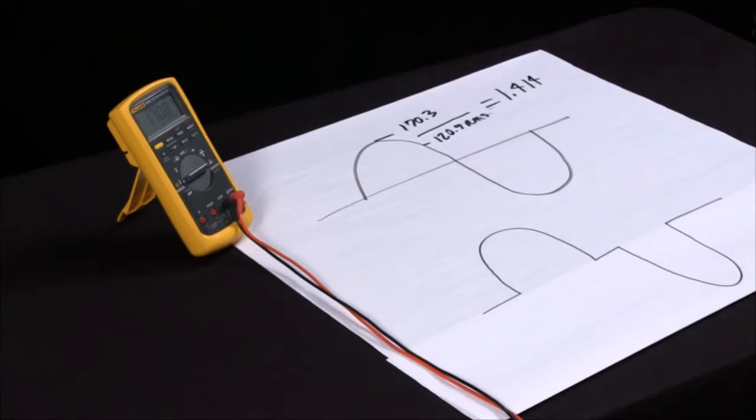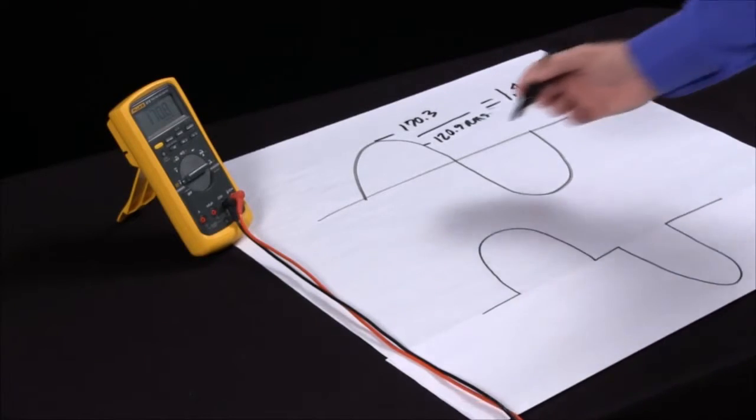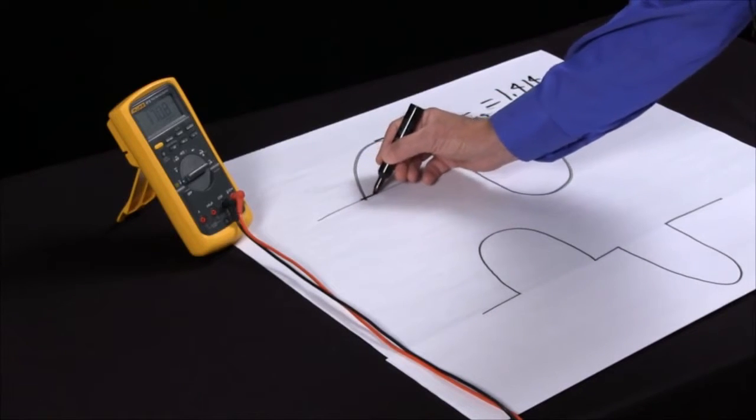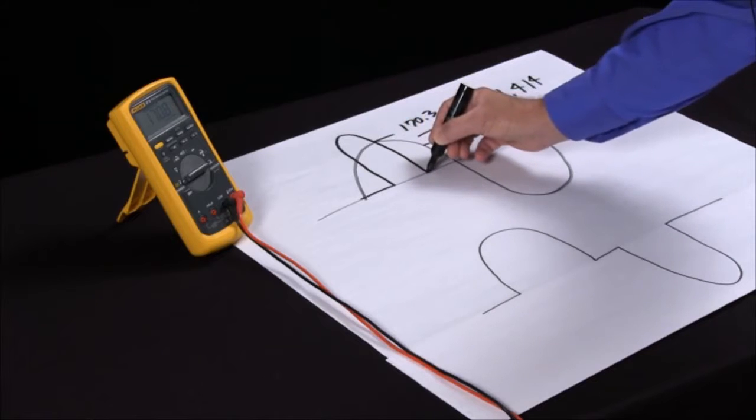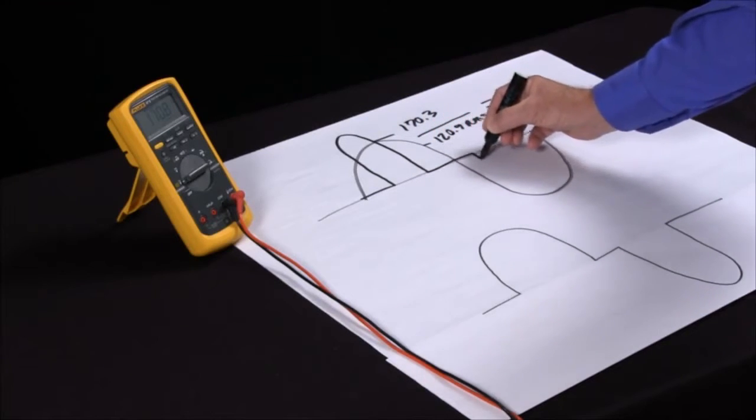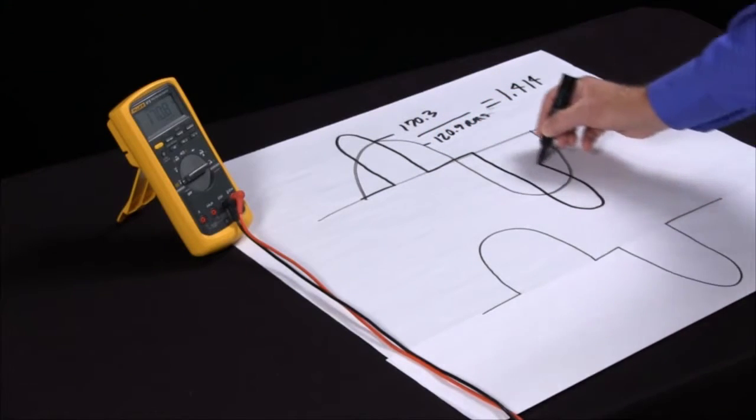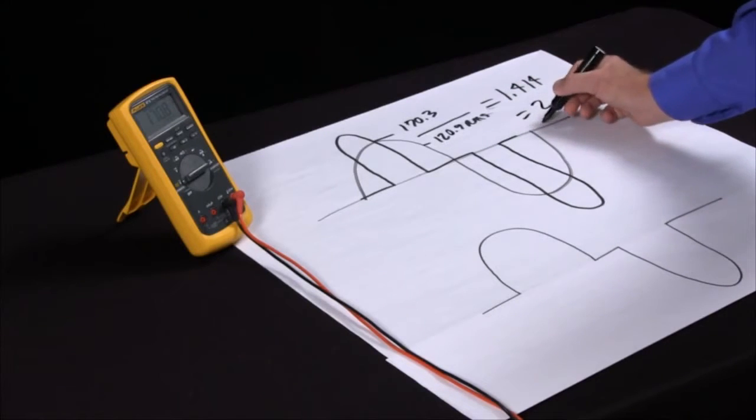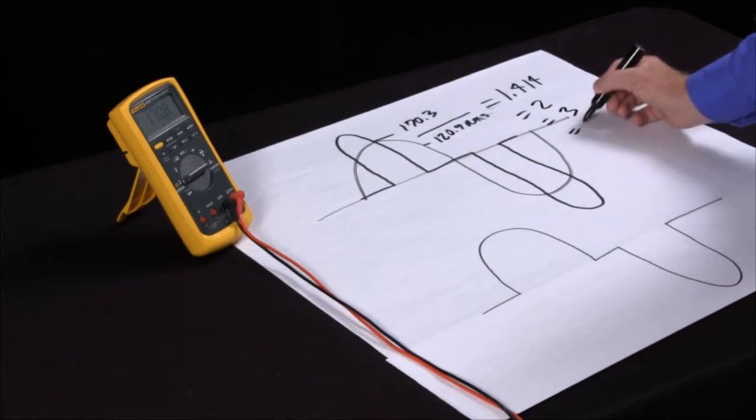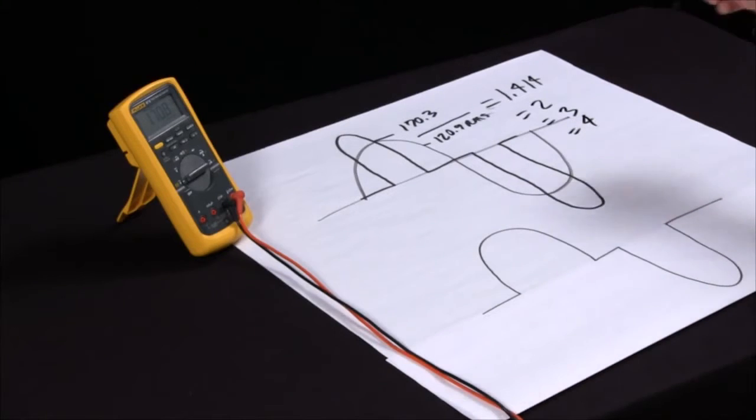Now if we have a signal that is distorted or has quite a bit of harmonics in it, what happens is the peak gets higher and the RMS gets lower. So when I look at this ratio, I will start to see a ratio that will be equal to 2, equal to 3, maybe equal to 4. This will be an indication that the higher the number is, the more harmonic distortion I have on the signal.